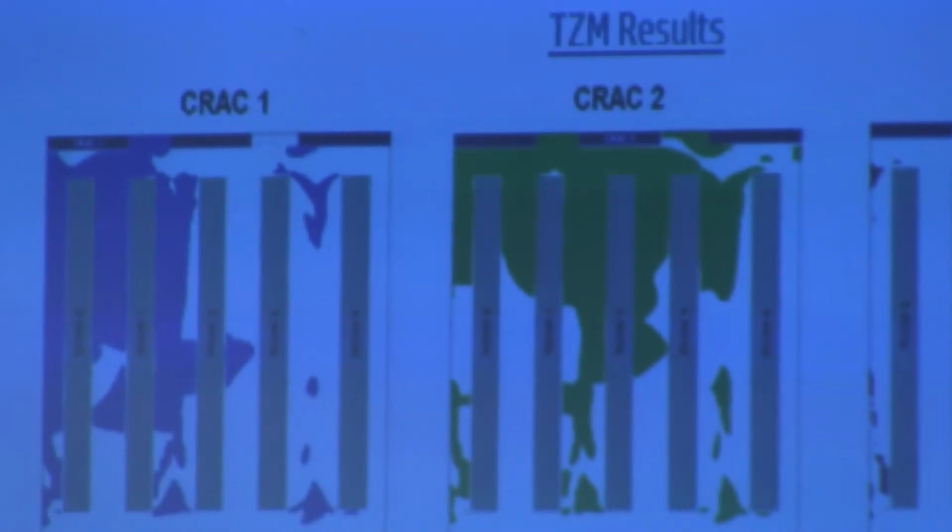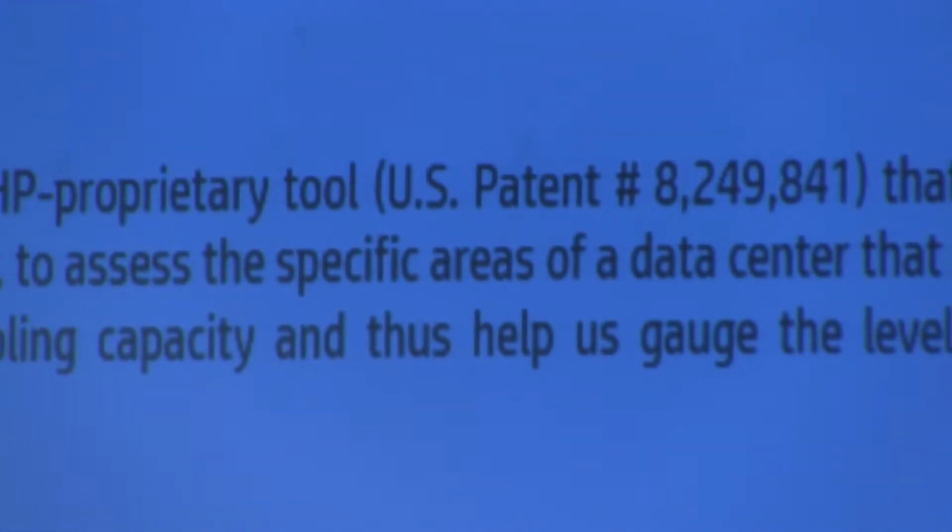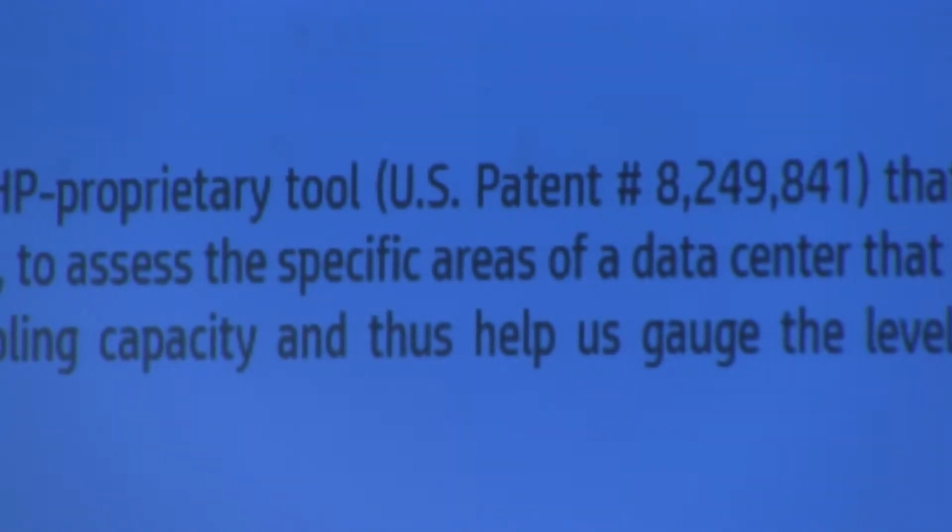So for any change in a degree that you give in your settings on your air handling unit, you are affecting the temperature in that location by a quarter of the degree, by 25% or more. It could be even by the same degree. So you can now see how the region that particular air handling unit has affects your IT equipment. And we can do those kind of plots and visualize that for any of the air handling units in your data center.